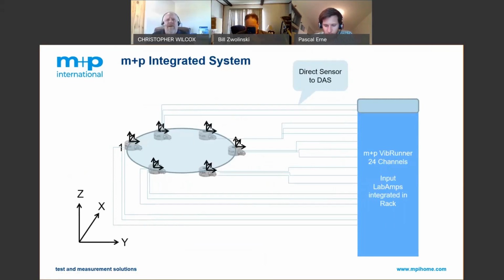We have now integrated the lab amps into our software, so the user has one place to store the data, sensitivities, ranges, and serial numbers, all documented at the end of the test for traceability. Another major benefit is that you no longer need to repatch anything once you start your test, from preload to end of test, sticking to one patch into your vibration control system.